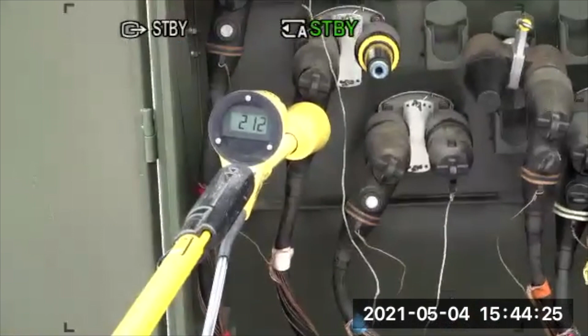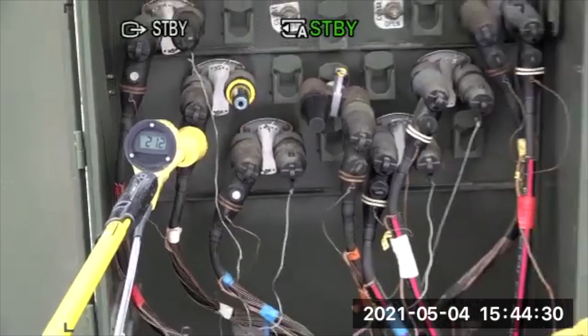Okay. So we've got about 212 volts phase to ground. We're going to verify we're energized, of course, but we also want to look at what our voltage is phase to ground on each elbow, because each elbow has a different fingerprint. The semicon material in the elbow causes it to have a different resistance.